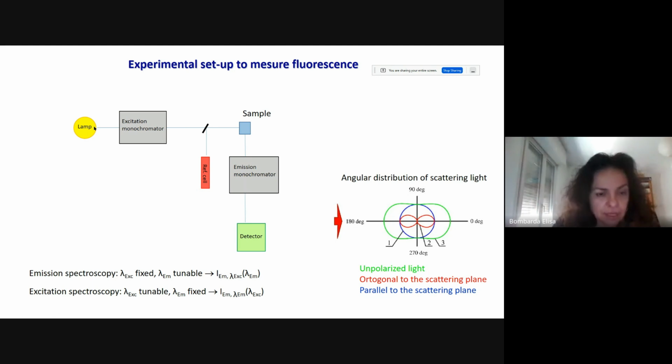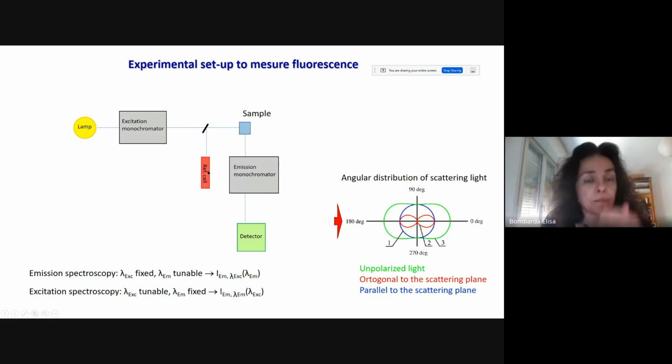The xenon emission has a spectrum, so there is not the same intensity per wavelength, but that would be an artifact on our spectra. So we have to compare. Using this reference cell, we can measure practically simultaneously the spectrum of the lamp, and the signal can be corrected.